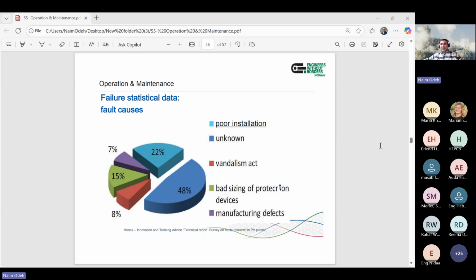Yes, the failure of the inverter can be significant, and the reasons for failures are many. As mentioned, there's wrong design, wrong installation, sometimes overload. It's about operations too. Sometimes people don't follow preventive maintenance of the inverters, which is basically just to check the inverter from time to time, keep the fan clean, and so on. We noticed this in some projects before. People think the inverter is just a machine that runs all the time and doesn't need anything, but actually it needs to be checked periodically. The statistics I shared are about records, but they don't mention the exact reason for failure of the inverter. I'm just giving examples of why inverters fail.